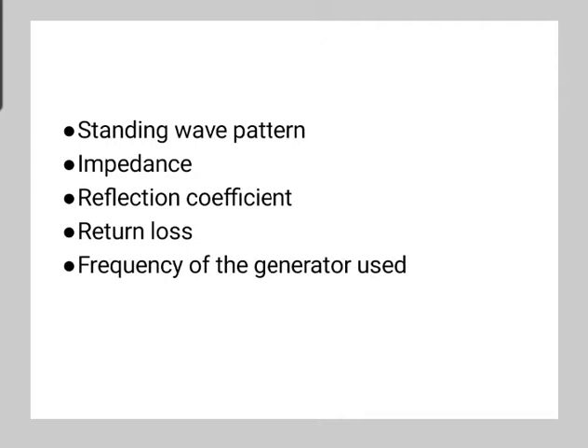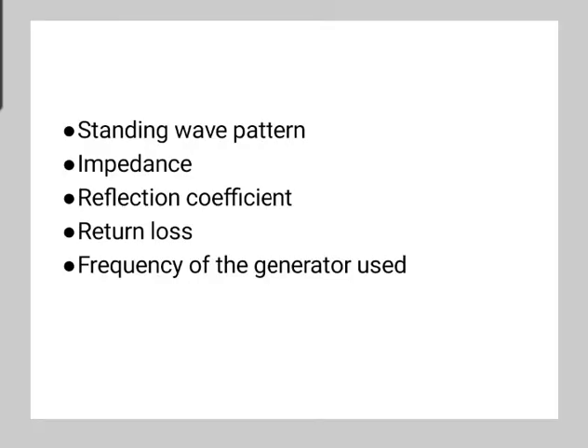The gain control may be used to set the reading to the required value. The overall gain is approximately 125 dB. The gain can be changed in multiples of 10 dB, and the VSWR meter has three scales. One is the normal SWR scale, which is used when the value of VSWR is between 1 and 4. The second is also a normal SWR scale, used when the value of VSWR is between 3.2 and 10. And the expanded scale, in dB, can be used for getting a more correct reading when the value of VSWR is less than 1.3. So the third scale is measured in dB, from 1 to 1.3.